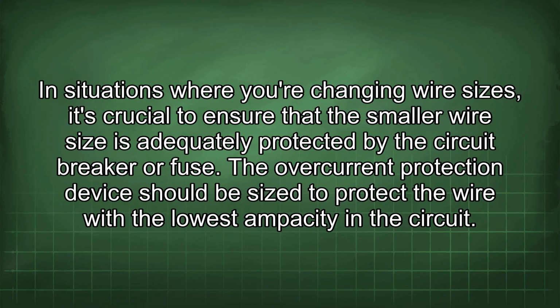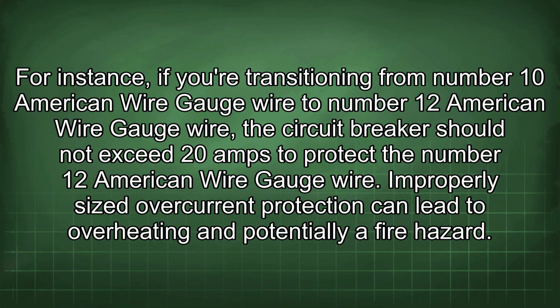In situations where you are changing wire sizes, it's crucial to ensure that the smaller wire size is adequately protected by the circuit breaker or fuse. The overcurrent protection device should be sized to protect the wire with the lowest ampacity in the circuit. For instance, if you're transitioning from number 10 American wire gauge wire to number 12 American wire gauge wire, the circuit breaker should not exceed 20 amps to protect the number 12 American wire gauge wire. An improperly sized overcurrent protection can lead to overheating and potentially a fire hazard.